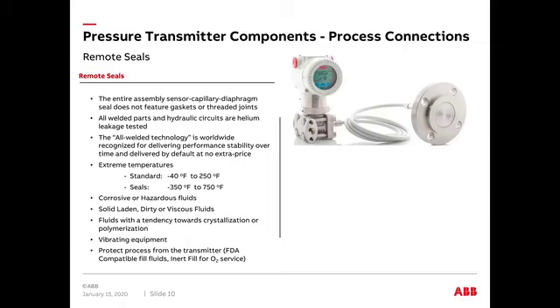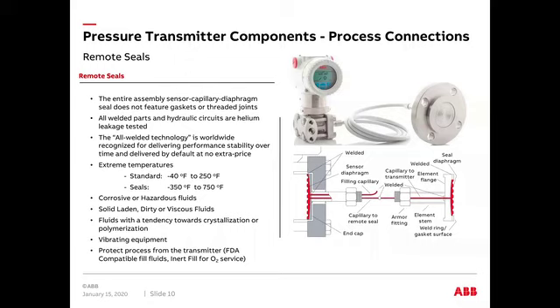There's fluids with a tendency to crystallize. There's vibration that you might have to overcome that you can do with a remote seal. And you might be in a situation, food and beverage wise, where you have to meet FDA requirements. And we do have the fill fluids and the inert fill and oxygen service and different types of things to meet all those industries. As you can see there in the diagram that I just added, those are the different points, the different connections that with some manufacturers you will find threaded or different types of seals, which over time may end up presenting a problem. But with ABB's 100% welded remote seals with the transducer, you don't have those issues.